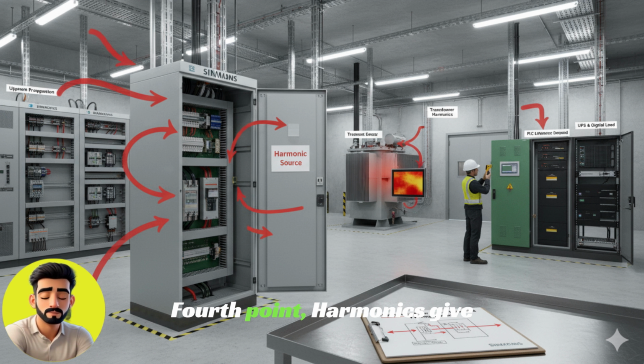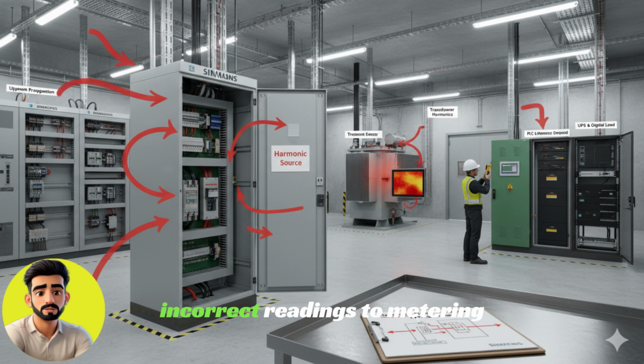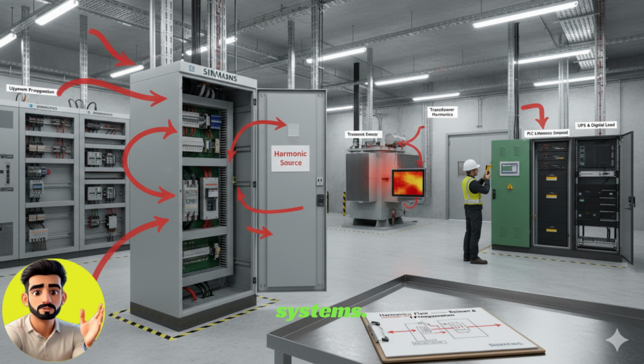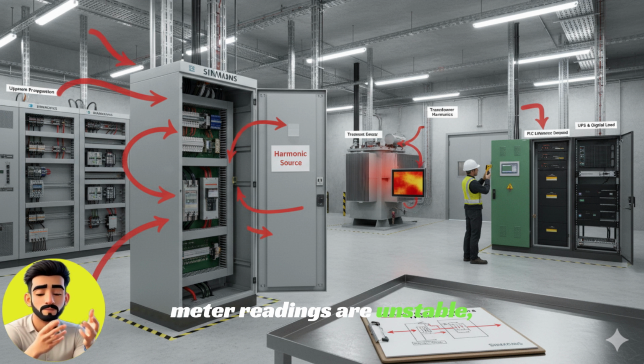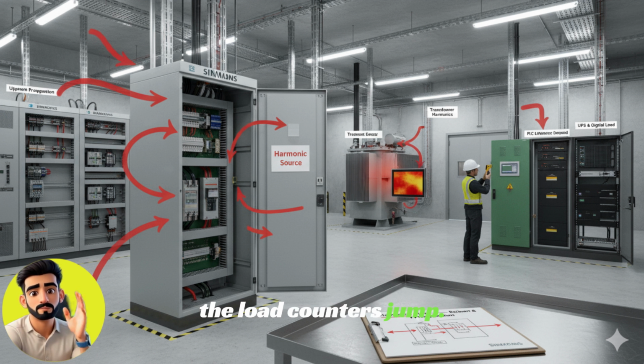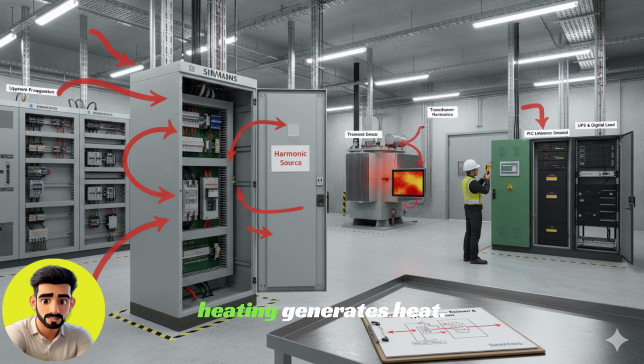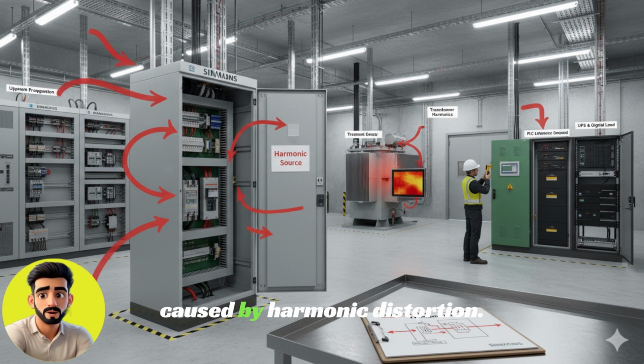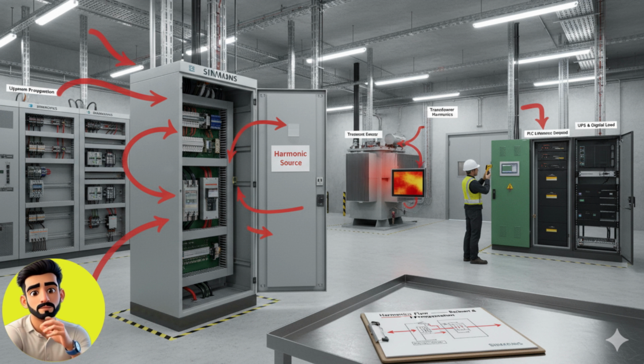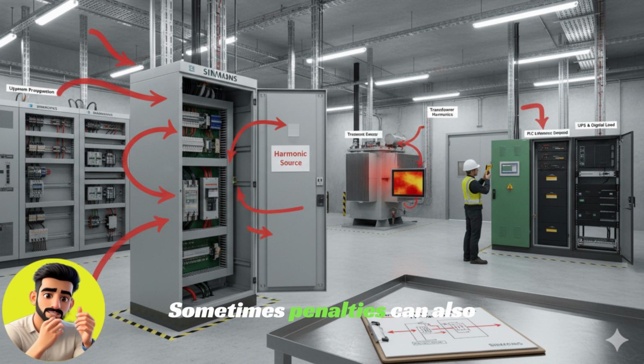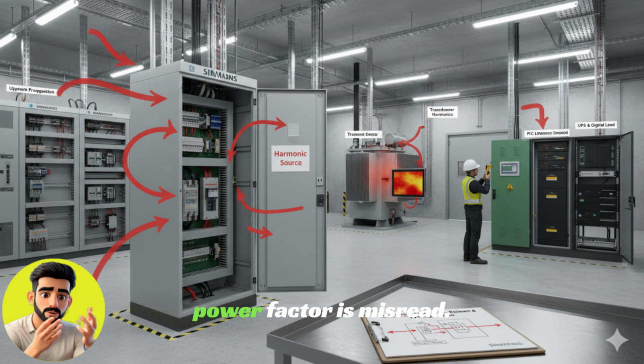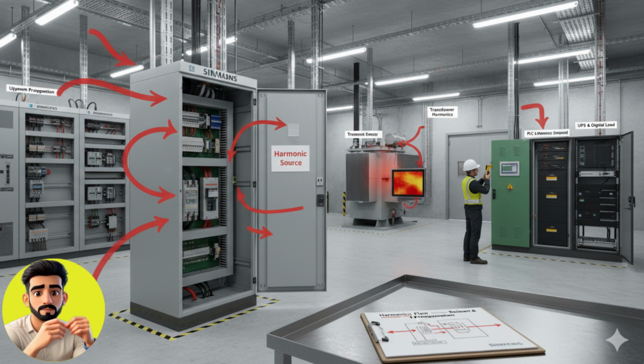Fourth point. Harmonics give incorrect readings to metering systems. You may have often seen that the power meter readings are unstable, and in some panels, the load counts jump. In the current transformer, heating generates heat. All these issues are caused by harmonic distortion. Sometimes, penalties can also be imposed because the power factor is misread.